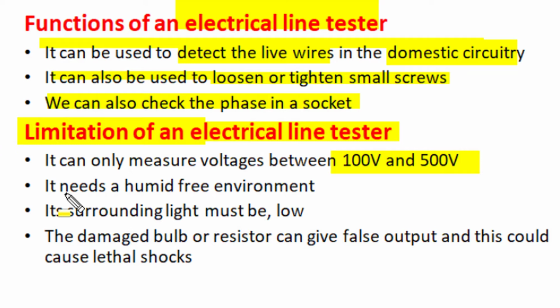In humid conditions, when the insulation of the surroundings is not proper, the line tester may give wrong indications due to the flow of leakage current through the neon bulb, and even in neutral test positions, due to surrounding leakage current passing through our neon bulb, we may get a visible indication. So it needs a dry, humidity free environment for testing purposes.